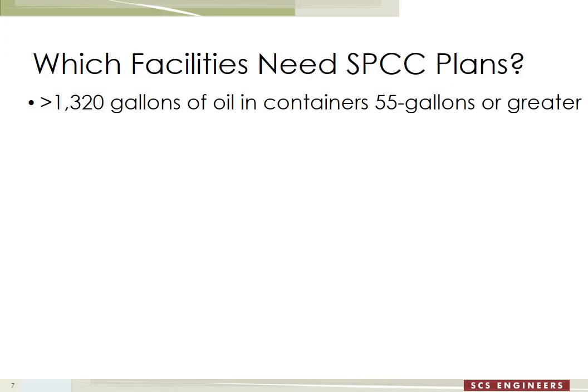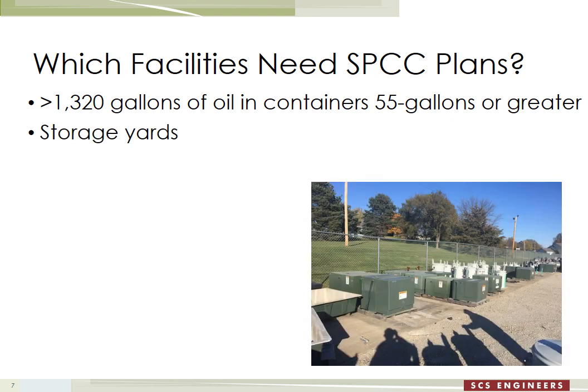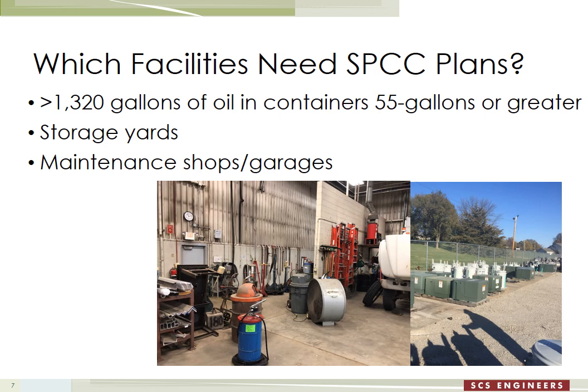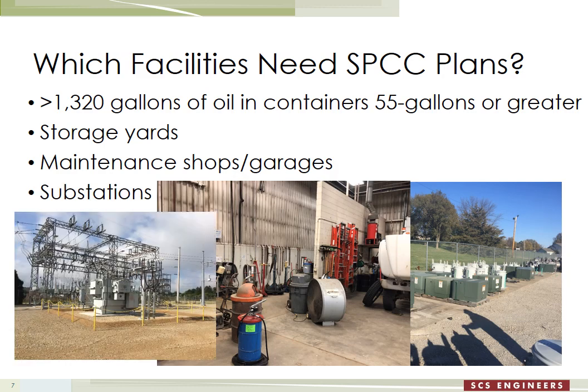What kind of facilities need SPCC plans? Again, it's that 1,320-gallon threshold in containers 55 gallons or greater. For you, that could mean storage yards where you store spare oil-filled electrical equipment, maintenance shops or garages where you've got 55-gallon drums, totes, or above-ground storage tanks. And of course your substations, where you've got large oil-filled equipment — transformers, circuit breakers, and other equipment.